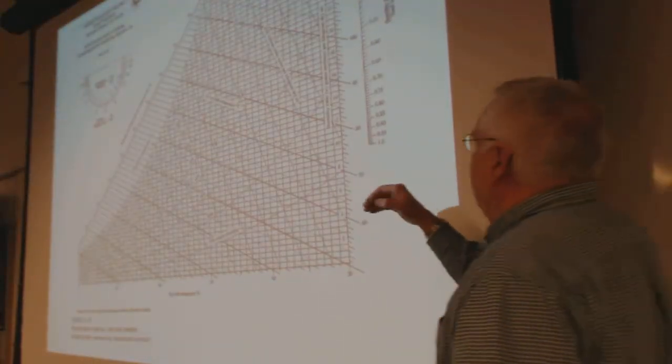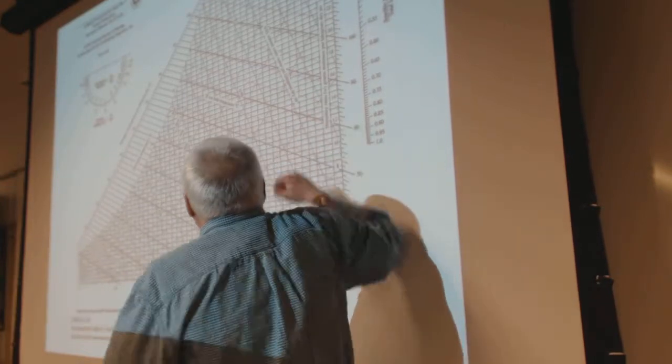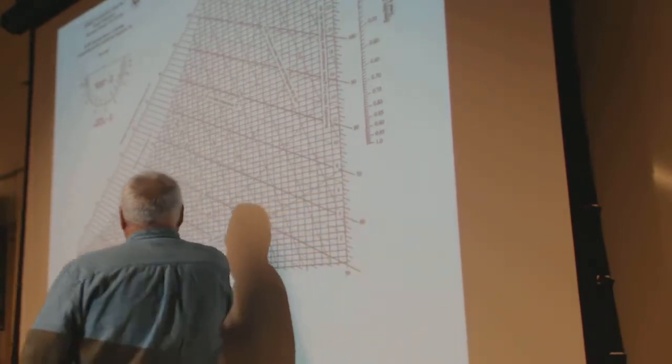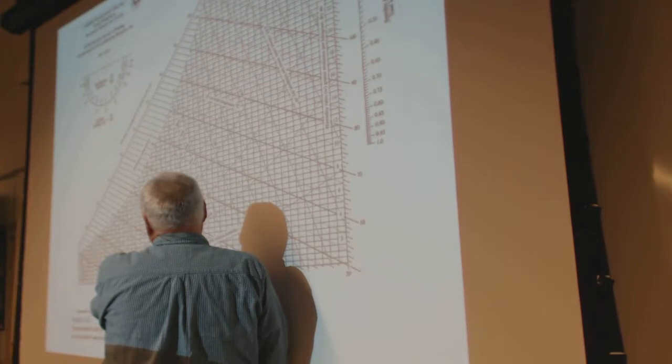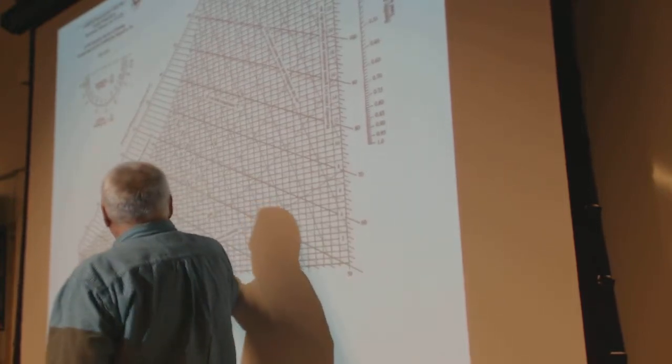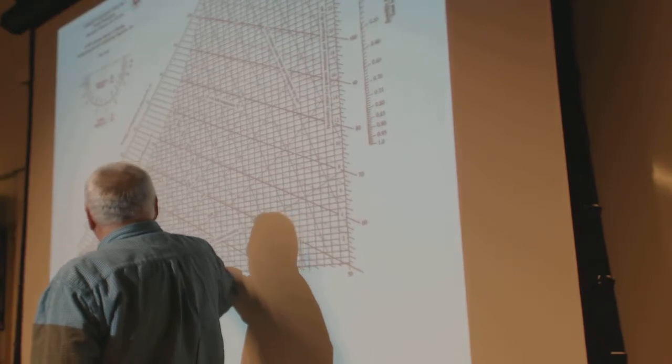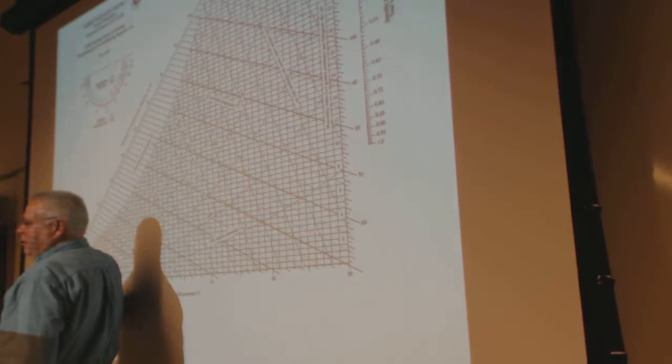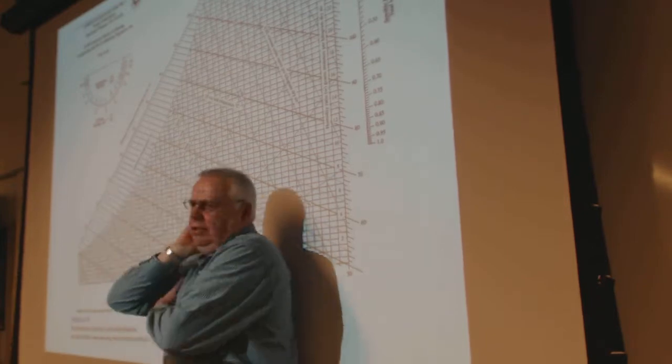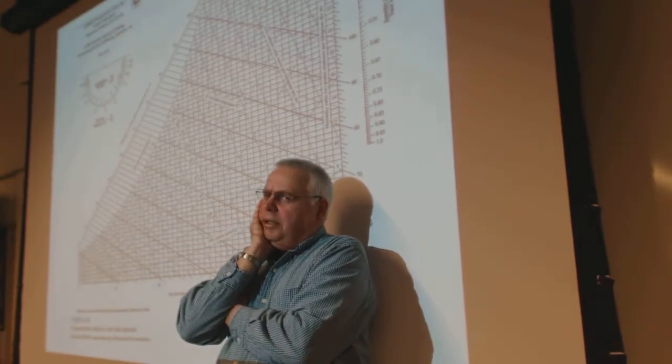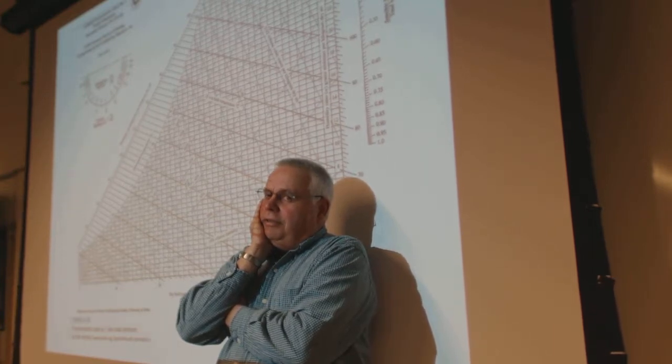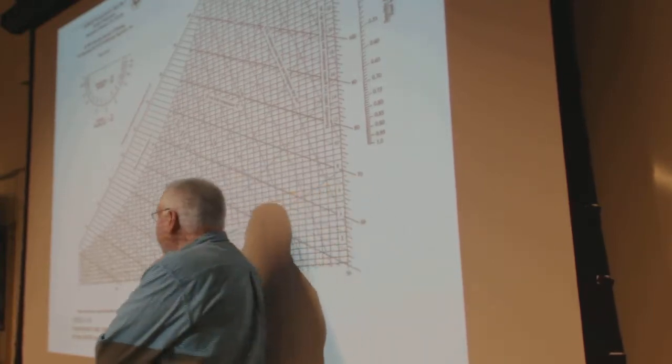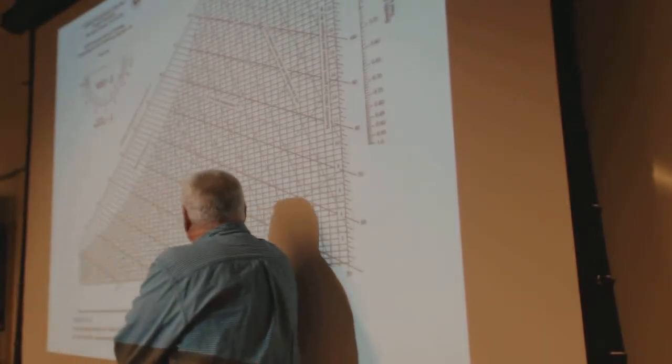So, on this chart, if you're adding moisture, you'd be going up. This is generally how that happens. So, for instance, if I had low humidity, like right now, we're at something like 22 degrees, and I bet you we're less than 20% relative humidity. And if, that means if I chilled this all the way down, that would only start condensing right about freezing. And, let's think about it. Is it raining outside? It's, so it's less than 100% relative humidity. If you took that air and brought it in and heated it up, even if it was 100% relative humidity, you'd probably end up about where we are right now.